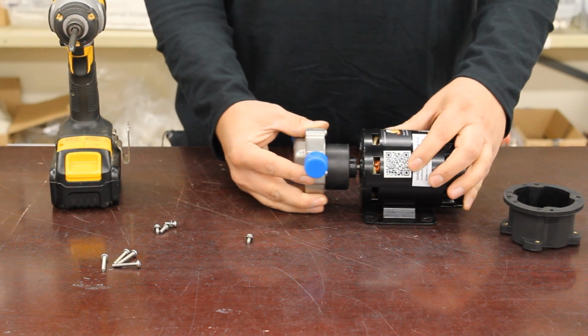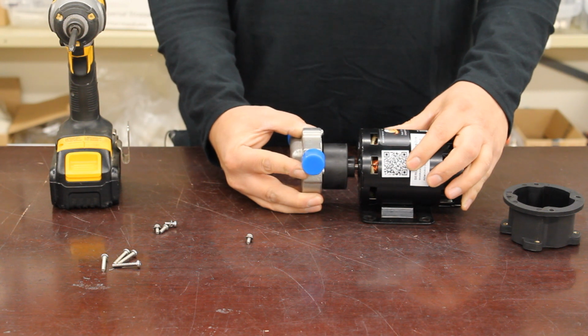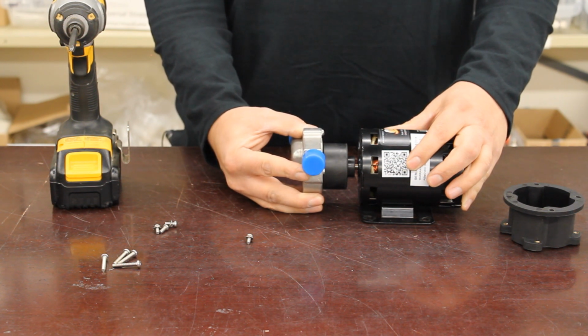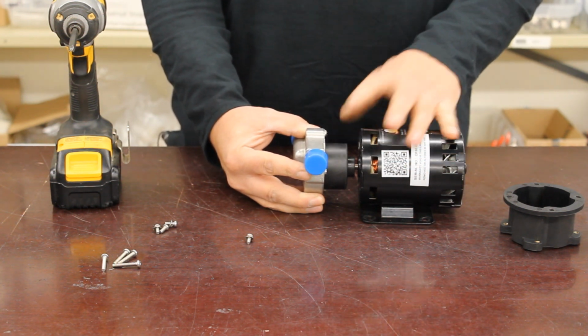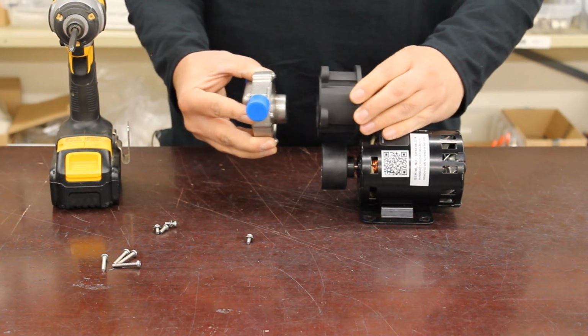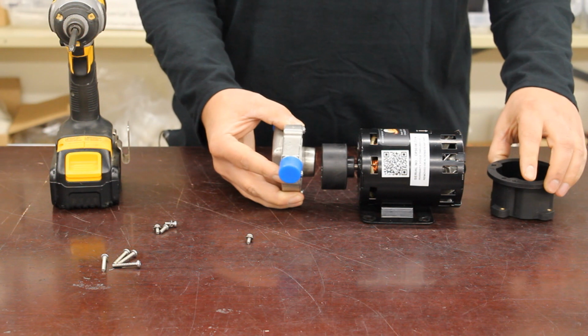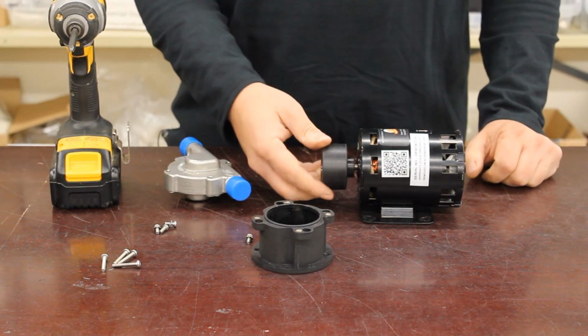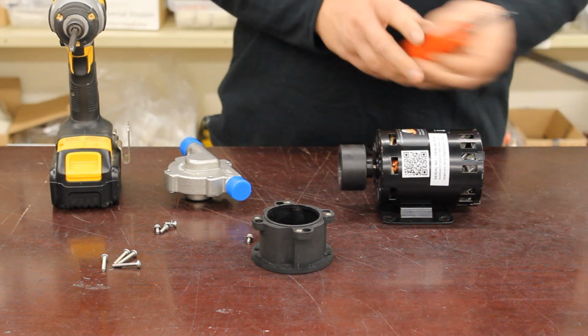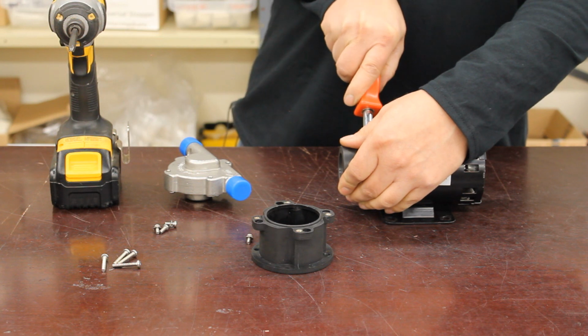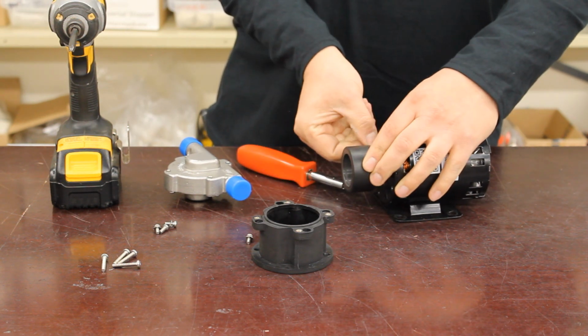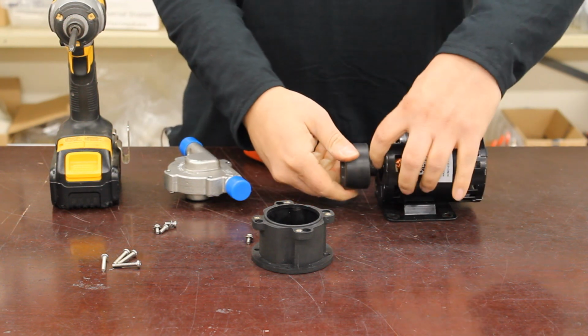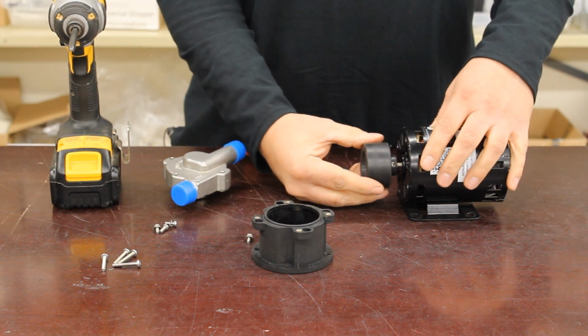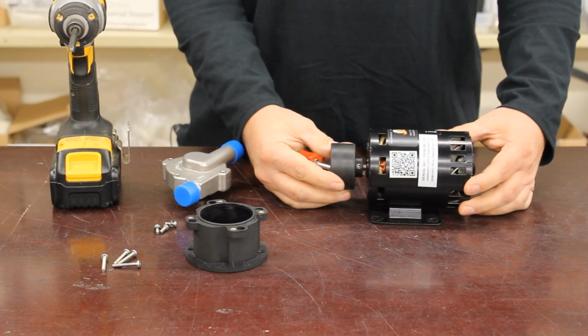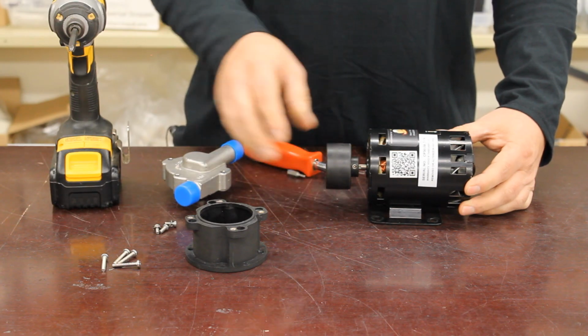For this to fully work and pump strong, that cup magnet has to be practically touching the back of the head. To have maximum magnetism, it has to be close tolerance. You can imagine that as this moves further away from the motor, you're moving the two magnets apart. So account for it by adjusting the cup magnet. It is held on to the motor shaft with an Allen key set screw. This is a 3mm Allen key, and there's a set screw right there. If you loosen that, you can take the cup magnet off. That also means there is a little bit of adjustability as far as the depth is concerned, so you can reposition this so that it comes out further.